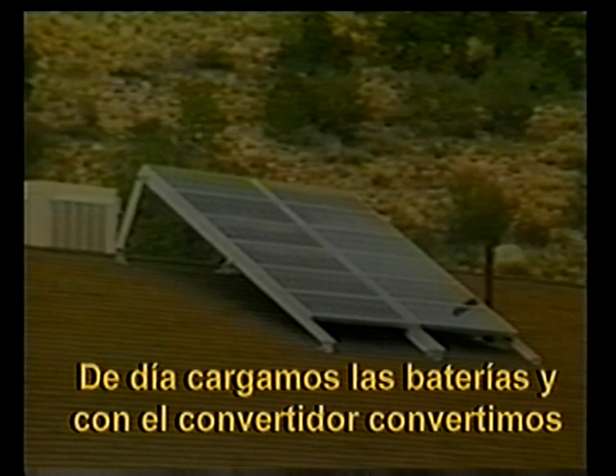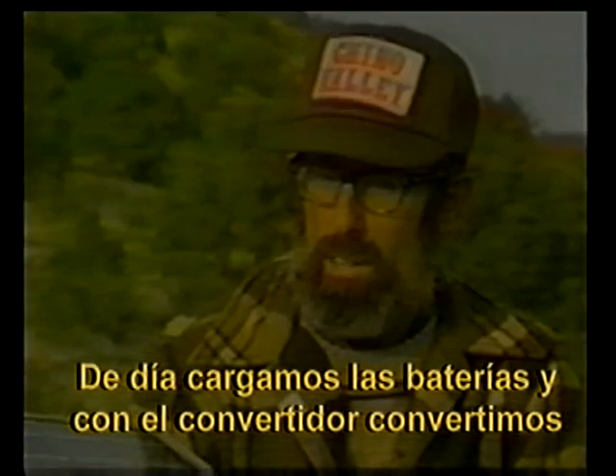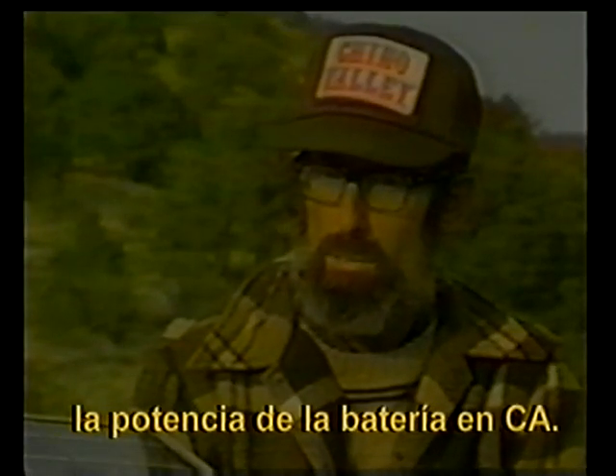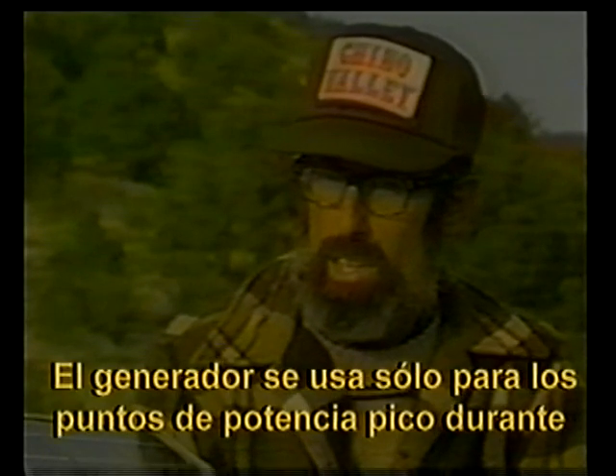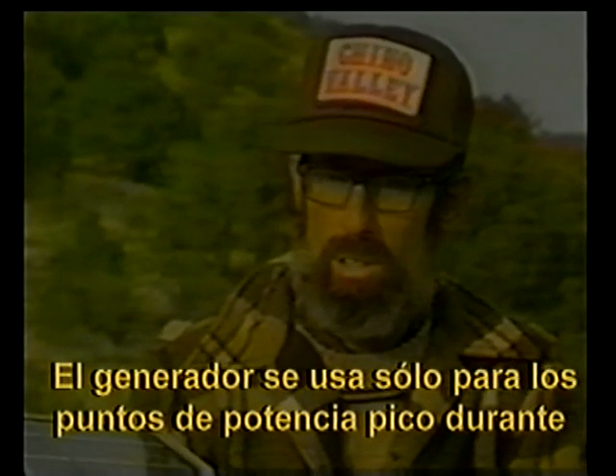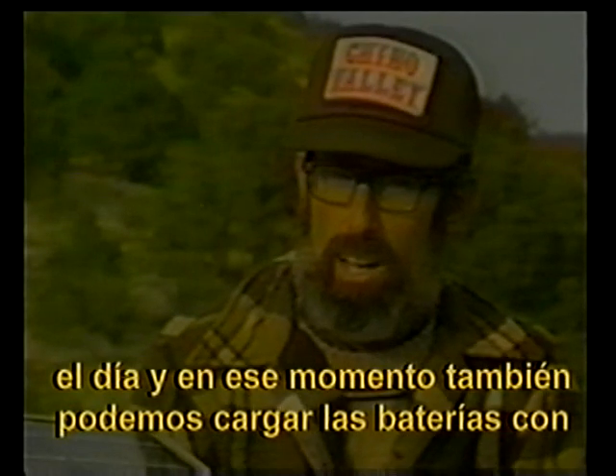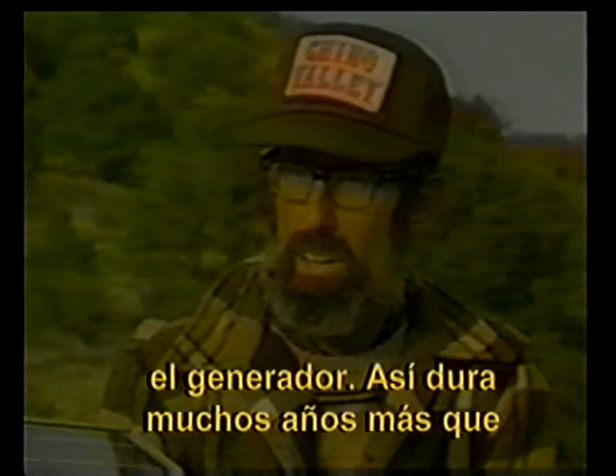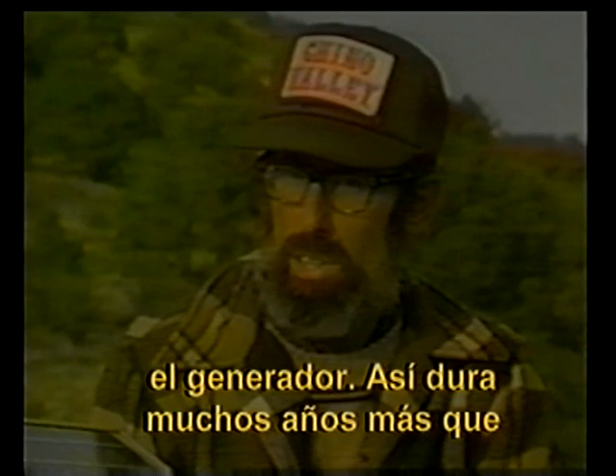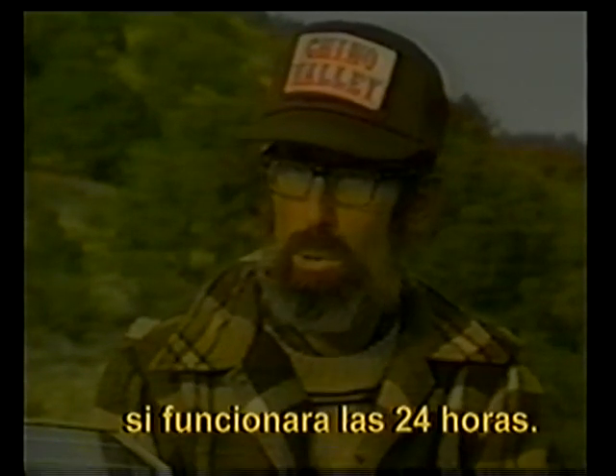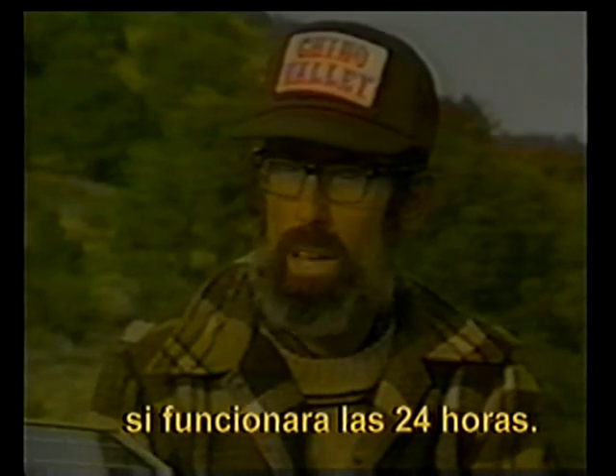We're charging batteries during the daytime and converting the battery power to AC power with the inverter. When the generator is needed, it is only for the peak power points during the day, and at that time we can also charge the batteries with the generator. So what we effectively do is make the generator last many, many more years than it would be possible when it runs on a 24-hour basis.